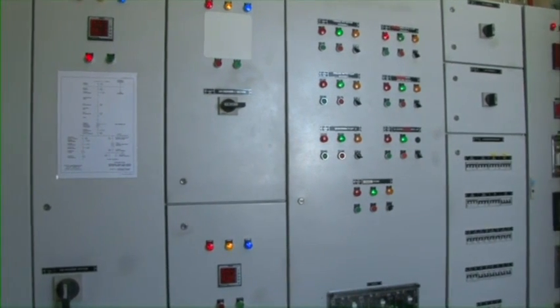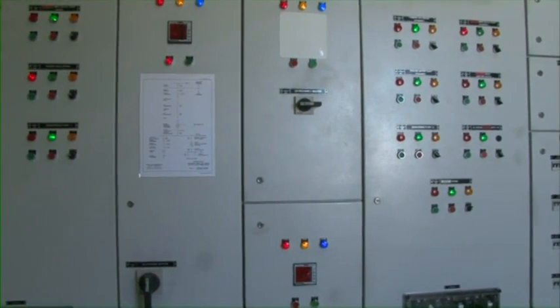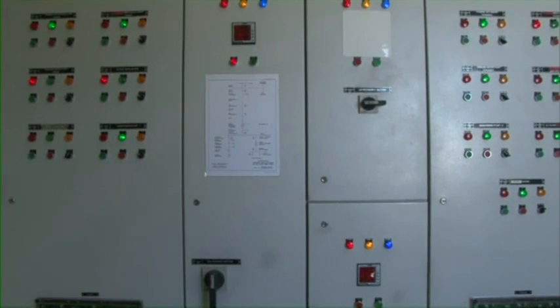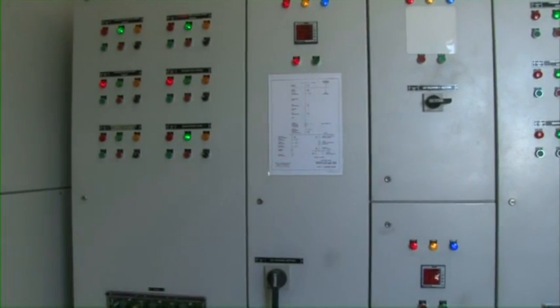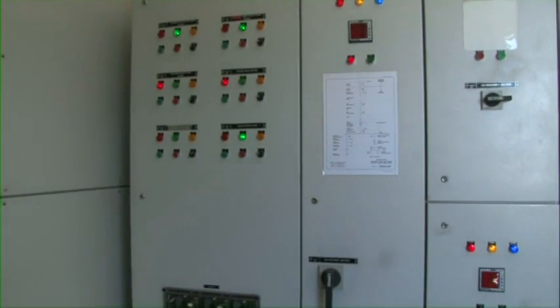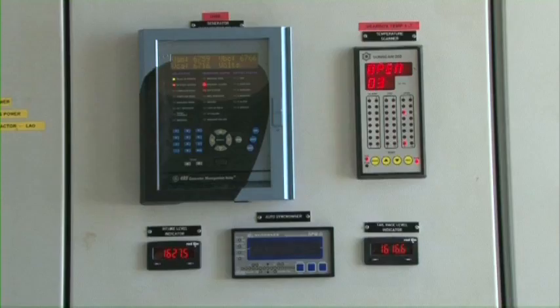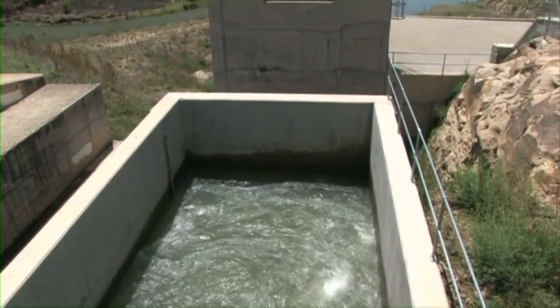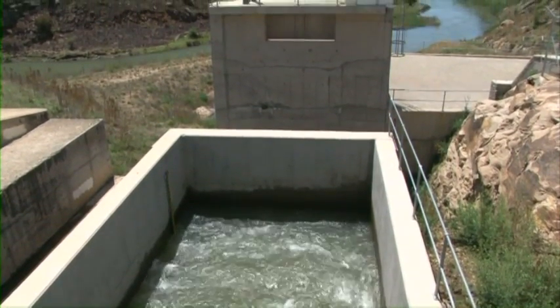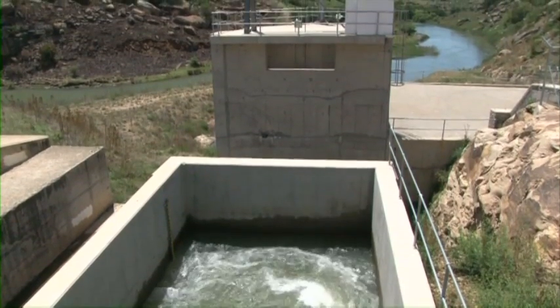This PLC can convert all these signals into alarm signals if it is required. In the event of anything going wrong, an alarm will sound in the power station. The PLC will then send the required signals to shut the power station down. The first thing that happens is the generator circuit breaker is disconnected from the Eskom grid, and the emergency gate will immediately fall down to close the water off from the turbine.